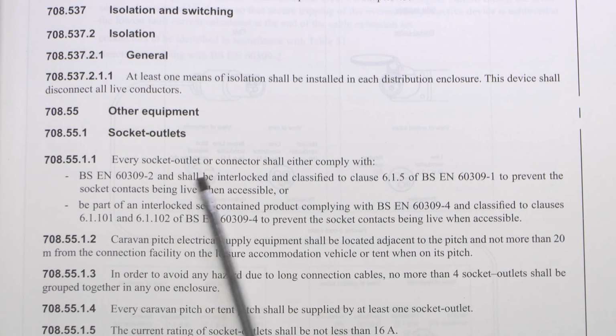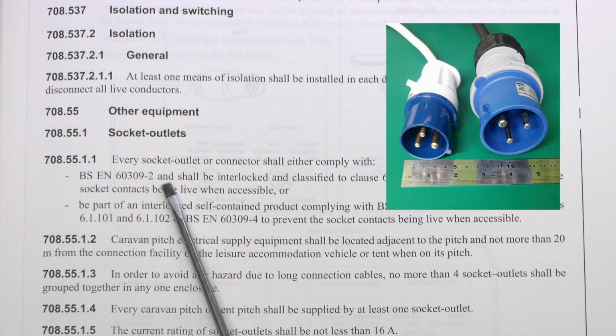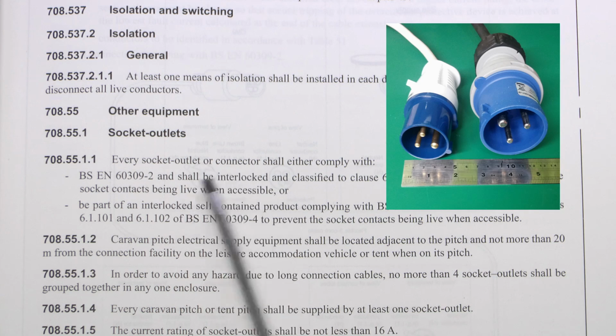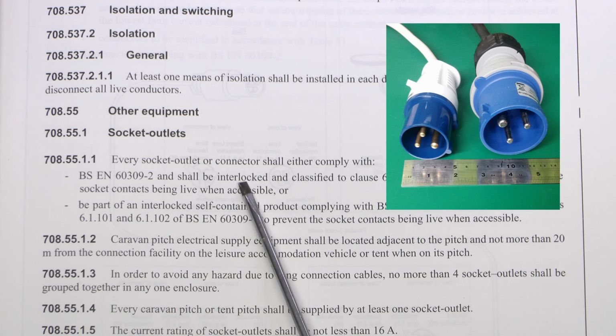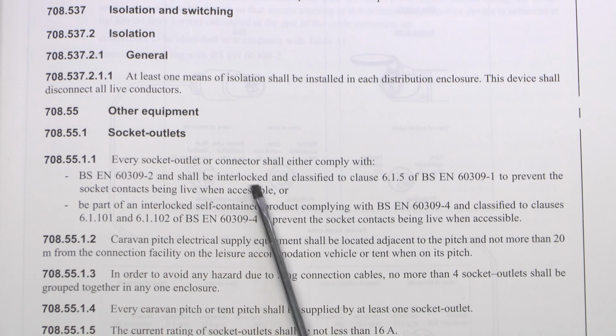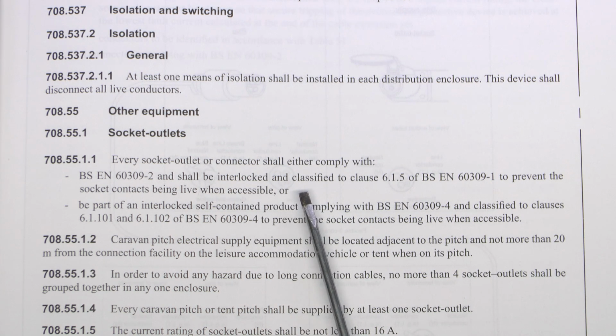Now these types of things are normally the round blue variety with the 3 pins. 16 amps is the most common type here, and the deal with them now requiring it to be an interlock variety is the type that when you actually insert the plug there, you can only do so when the switch is in the off position, and then when you turn it on you can't actually take the plug out of the socket until you turn the switch to the off position.